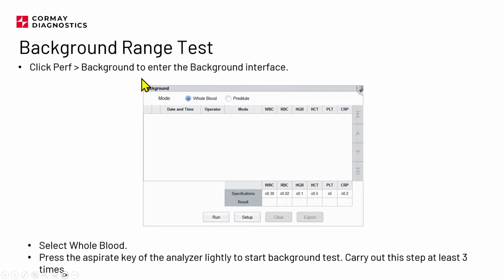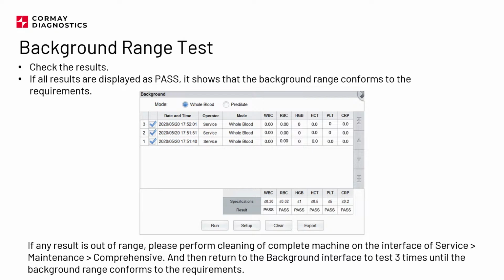What we need to do next, background. Check the background of the analyzer. So let's make 3 measurements. And if everything is fine, you don't need to do anything else. But if you see that some parameters are elevated, mostly the reason for that is that maybe your analyzer is not primed correctly yet. Maybe it needs another fluidic initialization. Or what you can do, also try to make a complete soak one more time and make another fluidic initialization, and then recheck it.